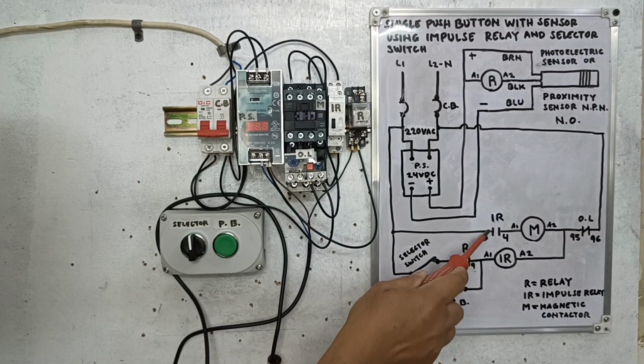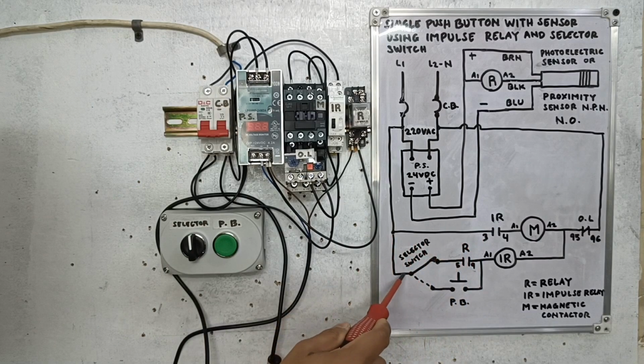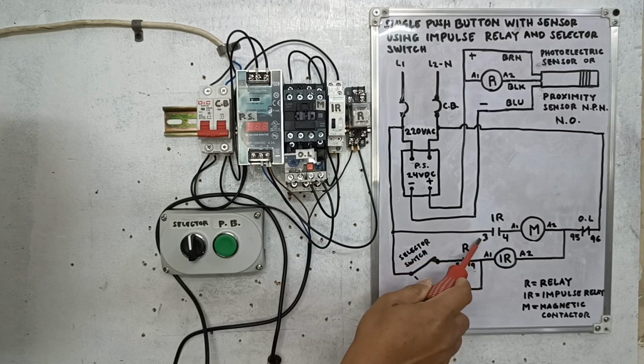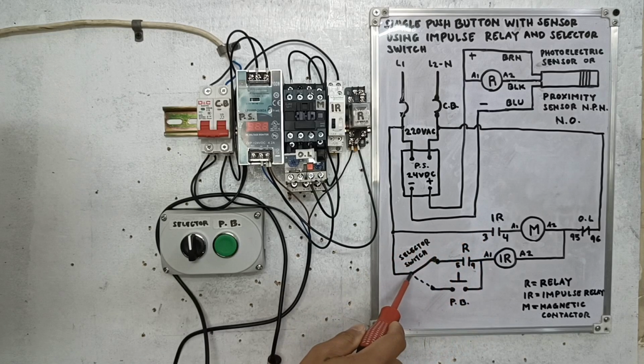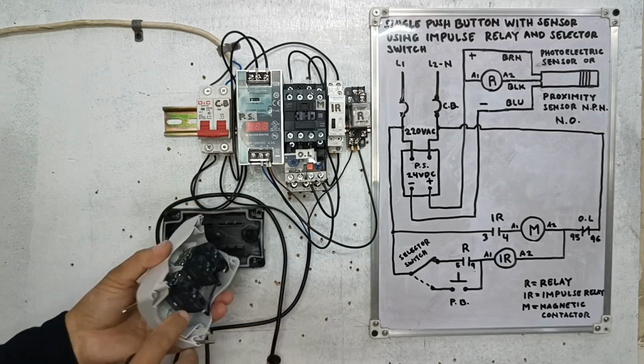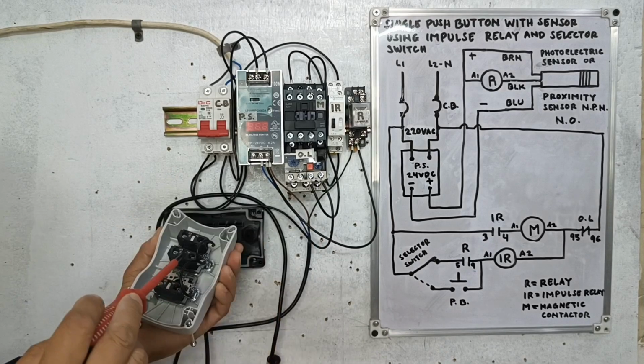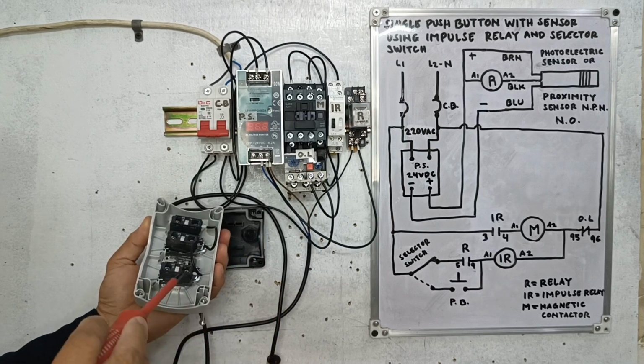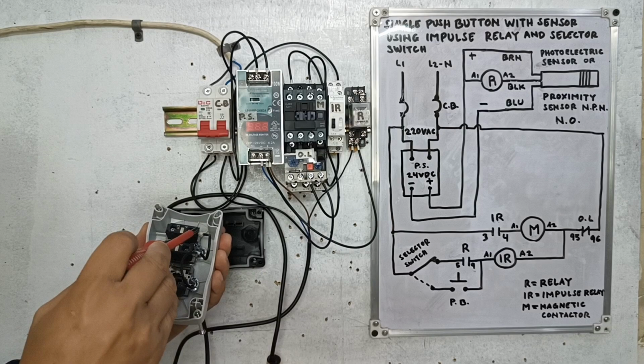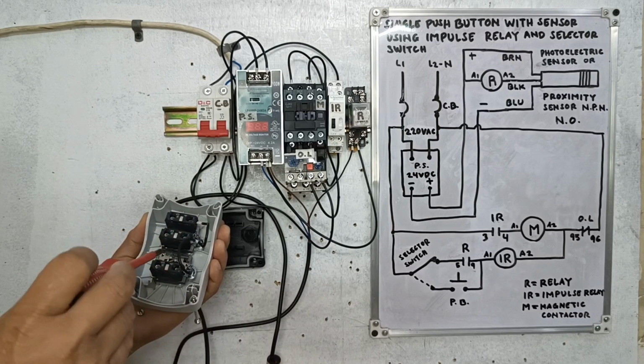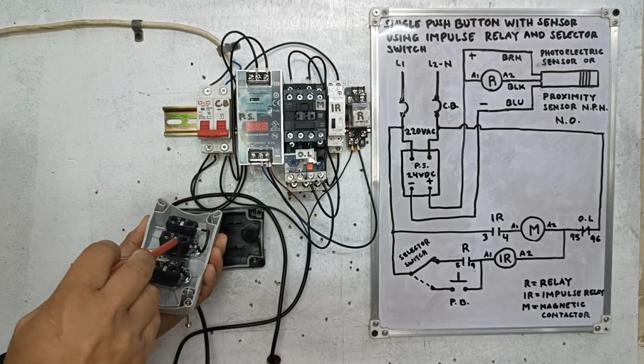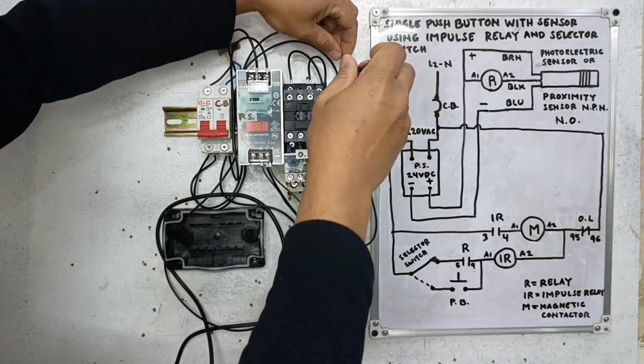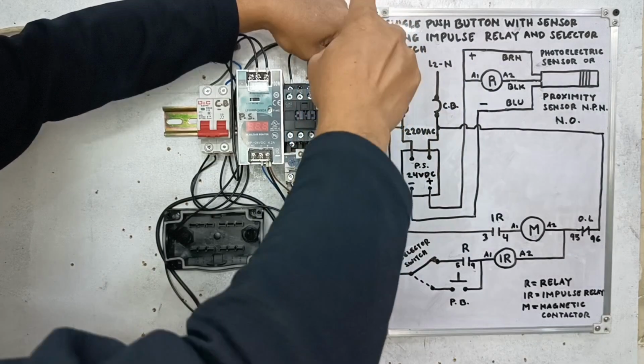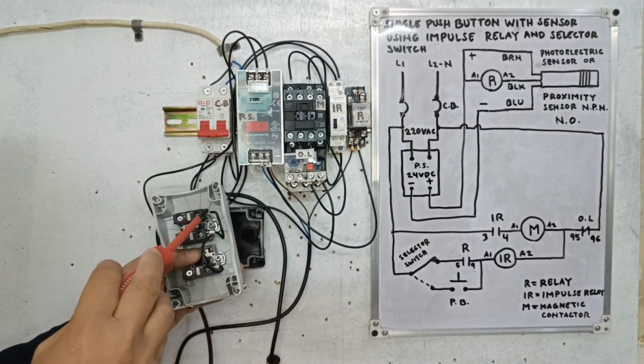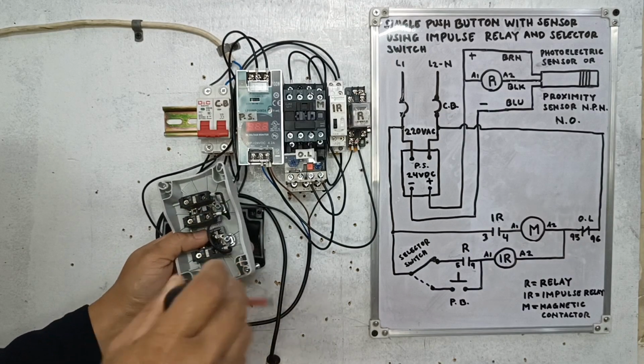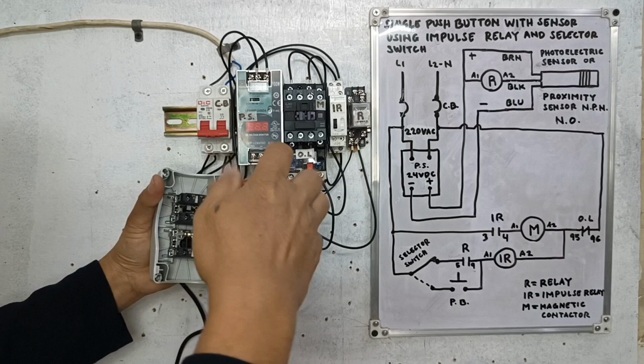The next connection, guys, from here going to the selector switch, from impulse relay number 3 normally open going to the selector switch. This is our selector switch. We're going to connect from here. Because I put a jumper already, we can connect from here, no problem, from here to here. We put it in the common. This one is the common. I put a jumper already. We can put from here, and then we tighten.